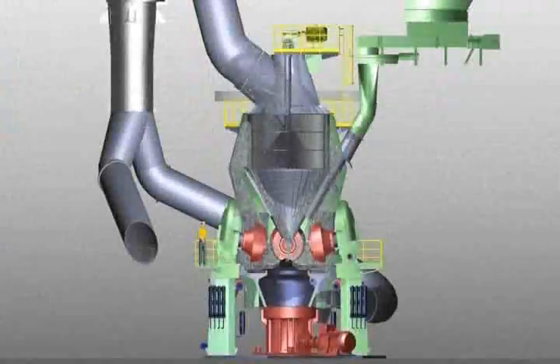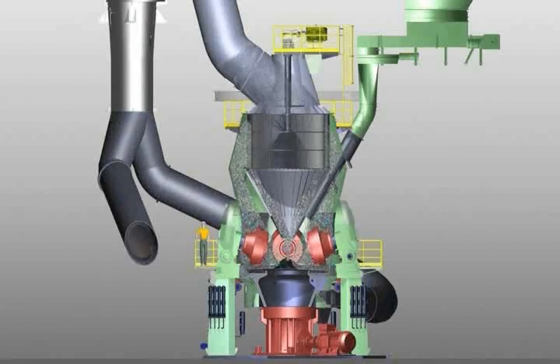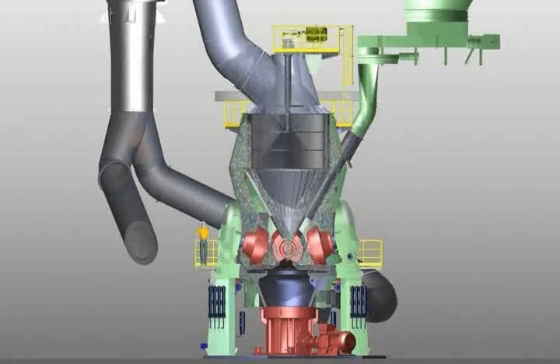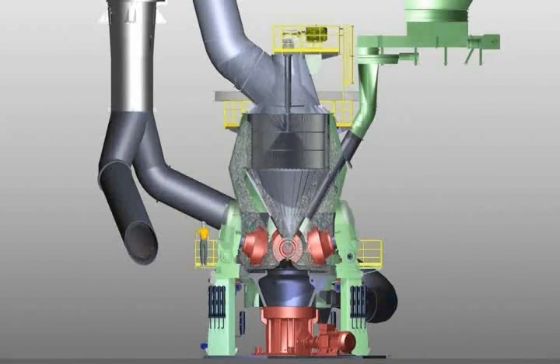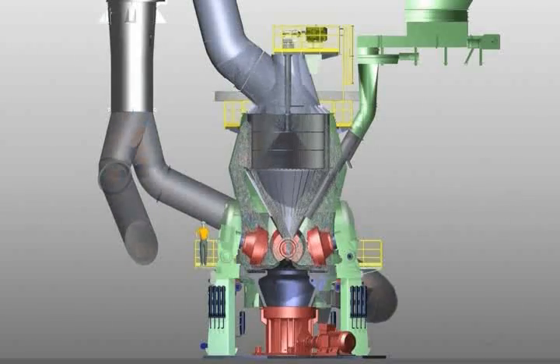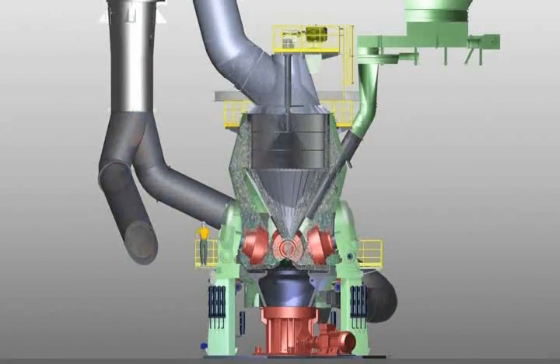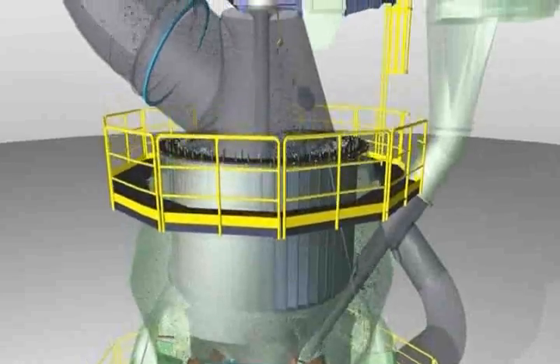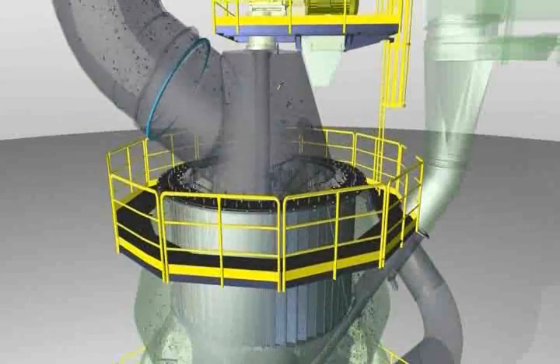The grinding rollers roll over the coal, which is comminuted by the force of the hydropneumatic roller spring system. The rotation of the grinding table throws the coal outwards to the area of the louver ring, which surrounds the table, where it is dried by hot gases. The coal is then transported to the classifier. When the coal particles come into contact with the hot gas, the water evaporates spontaneously. Based on the particular setting, the classifier rejects coal that has been comminuted into pieces which are still too large. The coal then falls back to the grinding table where it is comminuted again. The product is conveyed past the classifier and exits the Loesche roller grinding mill in the gas flow.